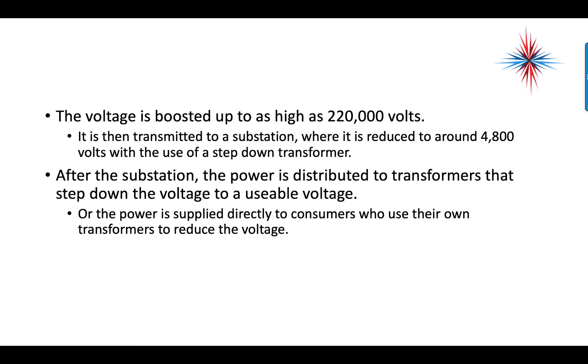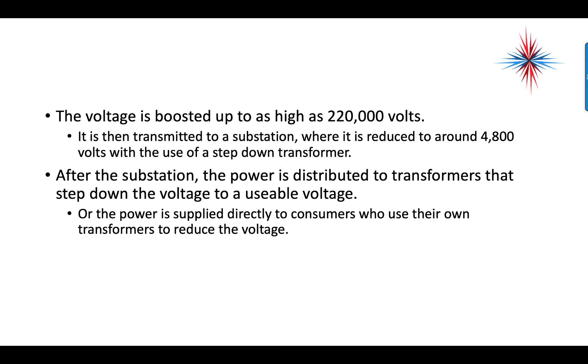The voltage is boosted up to as high as 220,000 volts. It is then transmitted to a substation where it is reduced to around 4,800 volts with the use of a step-down transformer. After the substation, the power is distributed to transformers that step the voltage down to a usable voltage. Sometimes the power is supplied directly to consumers who use their own transformers to reduce voltage — you see that more in heavy industrial applications.